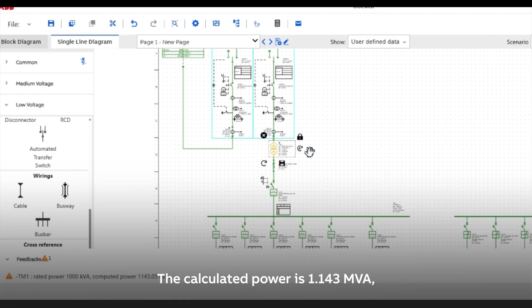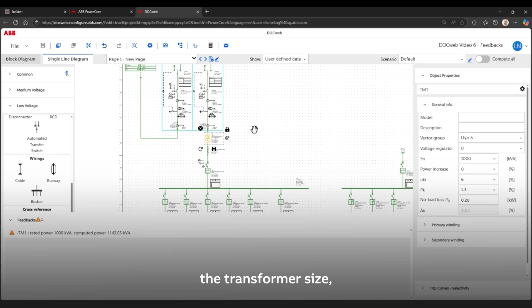Now, there's another feedback for TM1 about the power. The calculated power is 1.143 megavolt amperes, which is for the transformer. In a previous video, I showed how to use the transformer voltage regulator to fix a high voltage drop. This feedback means the transformer is too small for your loads. There are a few ways to fix this. If you can increase the transformer size, just unlock it and run the calculation. The software will show you what size you need.